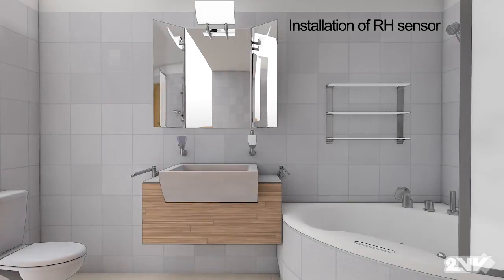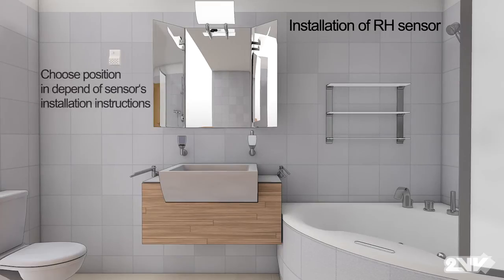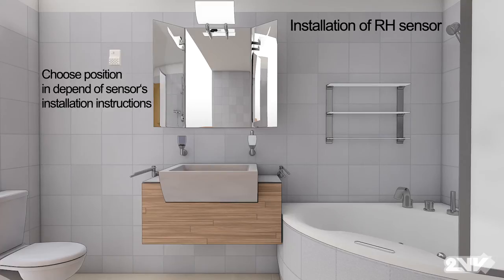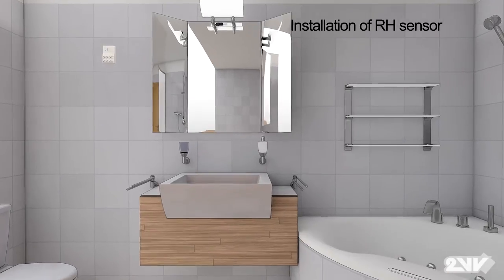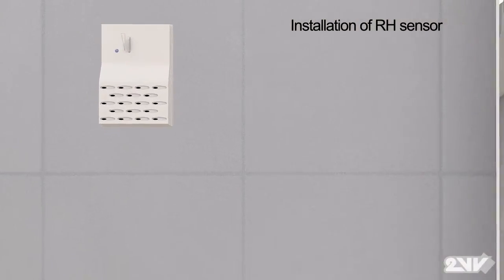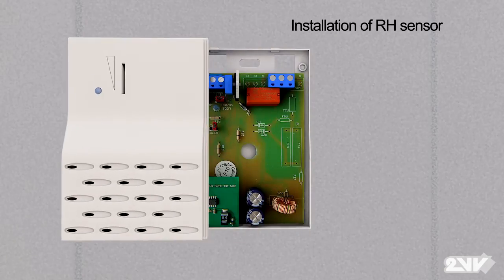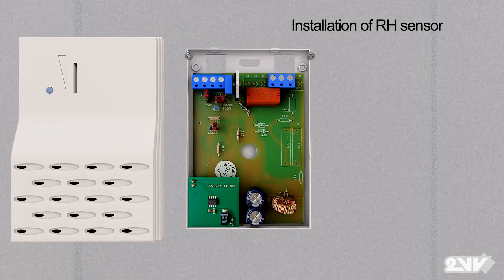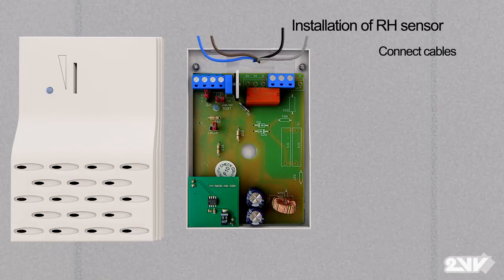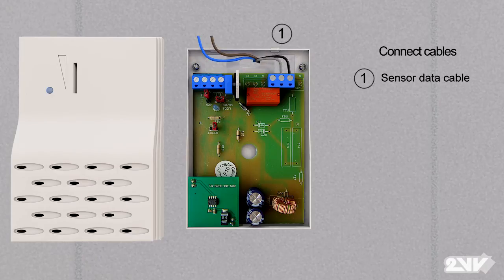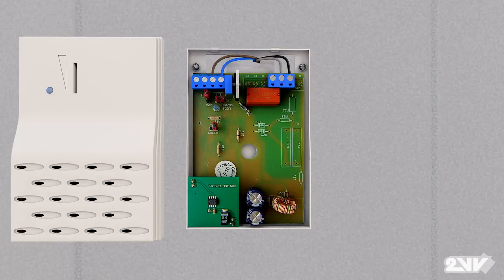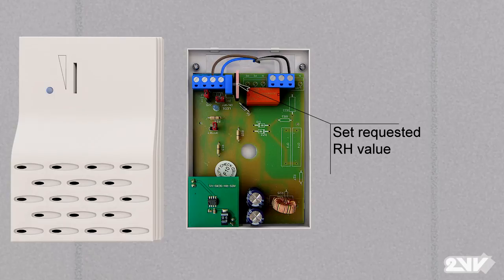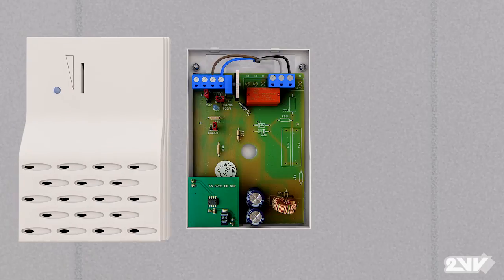When locating the humidity sensor, it should be mounted on a wall at a height of at least 2 meters. Do not place it in the shower over the bath or in the vicinity of the air inlet. Screw the sensor on the wall. Attach cables. The wheel on the top of the cover can be set to the desired humidity level at which the unit will activate.